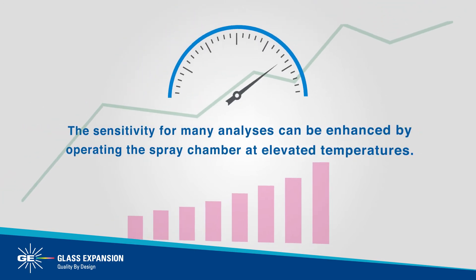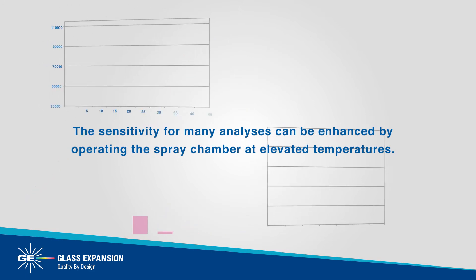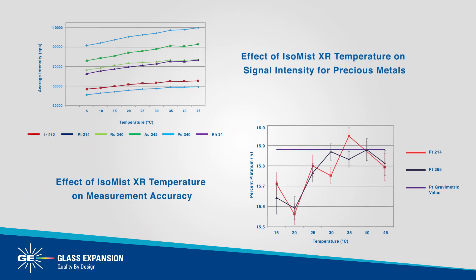The sensitivity from many analyses can be enhanced by operating the spray chamber at elevated temperatures. For example, the IsoMist XR showed improved accuracy and signal intensity for platinum and other precious metals at a temperature range of 30 to 45 degrees Celsius.